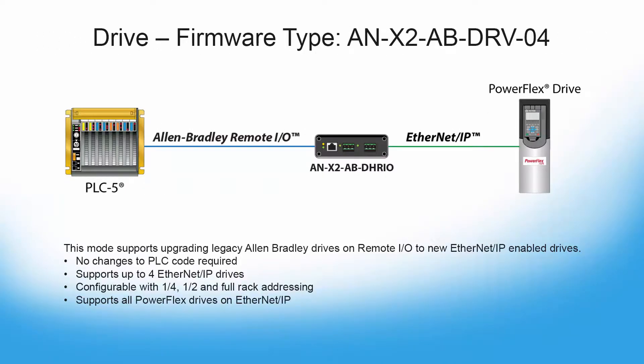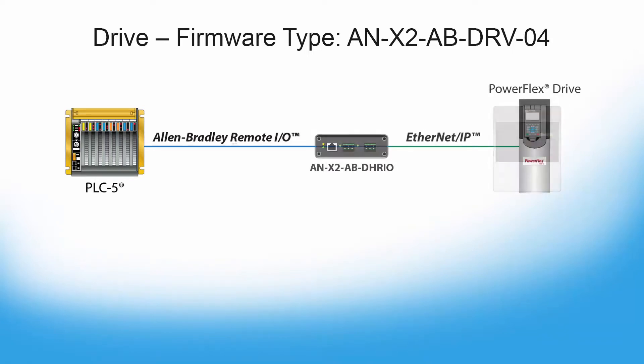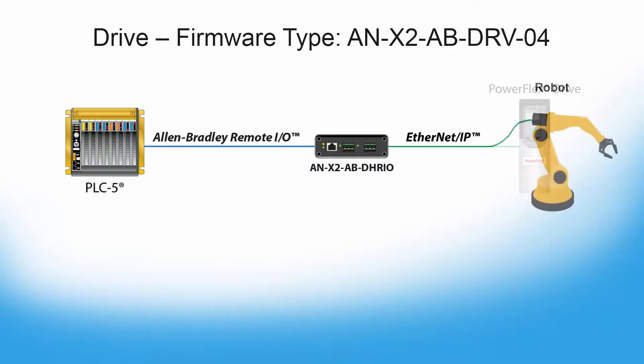ANX2ABDRV04 is intended primarily for connecting PLCs on RIO to PowerFlex drives over Ethernet IP. It's possible to use other drives on Ethernet IP, but PowerFlex drives are the model. This firmware can also be used if you're migrating from an old RIO robot to a new Ethernet IP based robot.